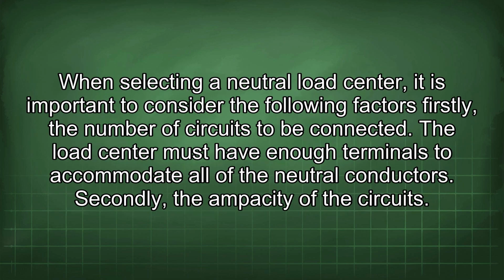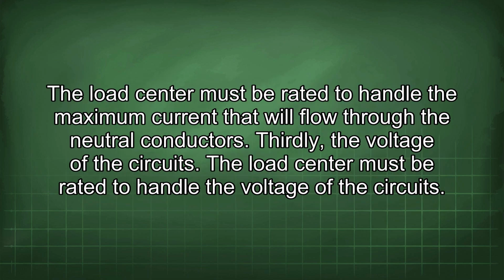When selecting a neutral load center, it is important to consider the following factors. Firstly, the number of circuits to be connected. The load center must have enough terminals to accommodate all of the neutral conductors. Secondly, the ampacity of the circuits. The load center must be rated to handle the maximum current that will flow through the neutral conductors.